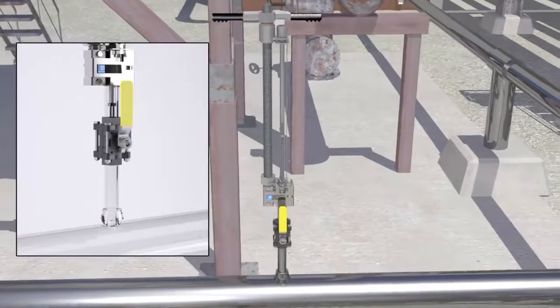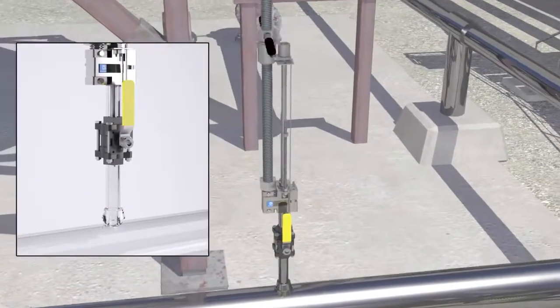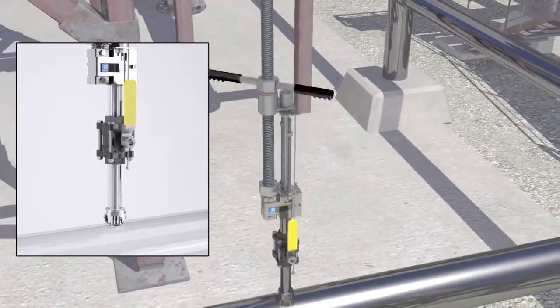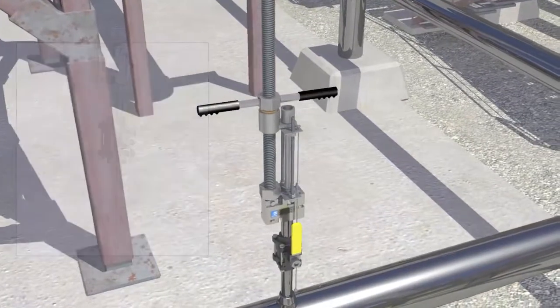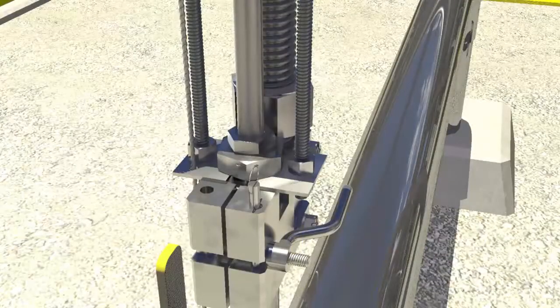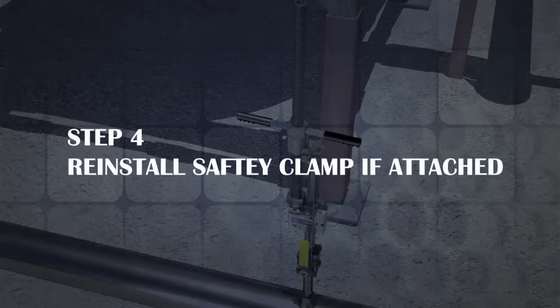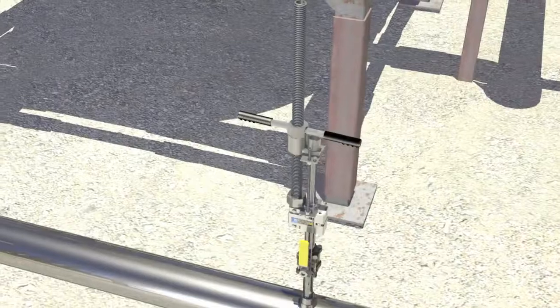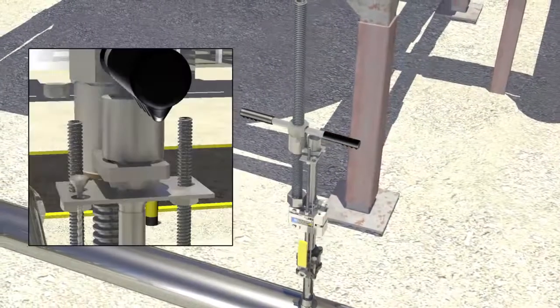Insert the probe by rotating the handle nut in a clockwise direction until the desired insertion depth is obtained, and then orientate the probe in the flow as required. Tighten the 1-inch hex locking nut 3/4 turn past hand tight and the 1.5 inch hex stuffing nut 1/2 turn past hand tight. Step 4. Reinstall safety clamp if attached. When the probe has a safety clamp kit, then reinstall the jam nuts onto the threaded rods.